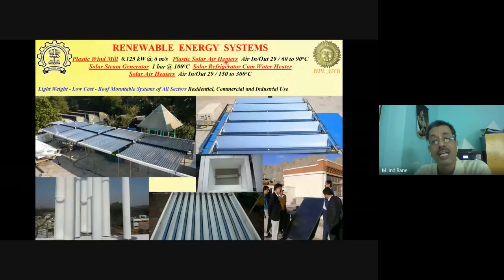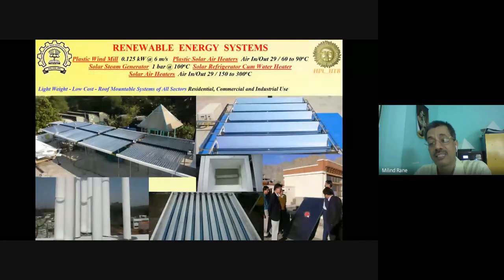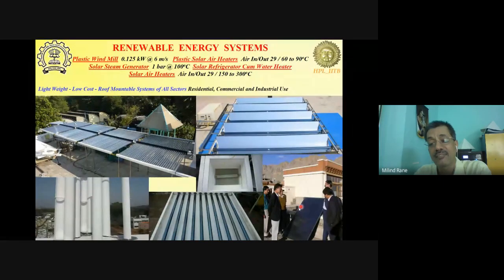We have plastic solar air heaters. As you can see in Leh Ladakh, these collectors, even in minus 40 degrees centigrade, minus 30 degrees centigrade, we could give 40-degree warm air for space heating. Okay. And then solar steam generators, as you can see here, these are heat pipe based steam generators. Okay. And then solar air heaters, which can heat up air right from ambient temperature to 150 to 300 degrees centigrade. We have gone up to 360 degrees maximum in a single pass in these things. And note that the 1.2 meter square collector here was driven with only a 14-watt fan, okay, which was a PV operated fan to get the hot air delivered.